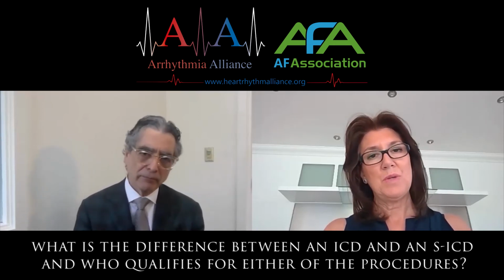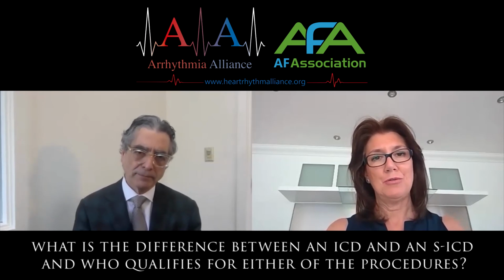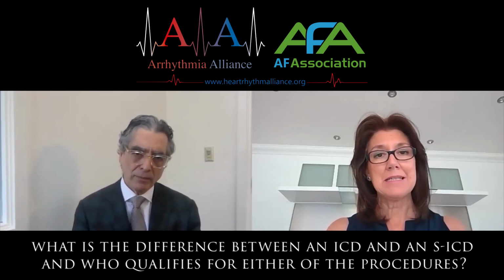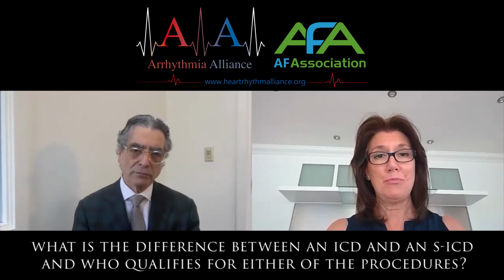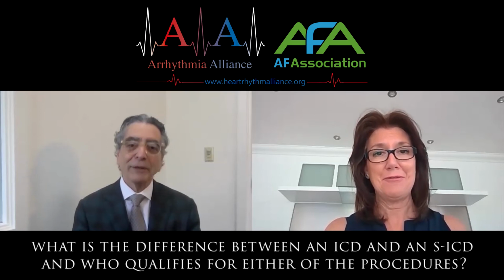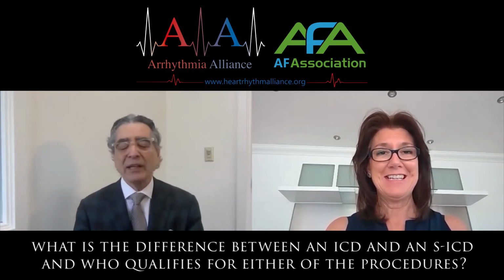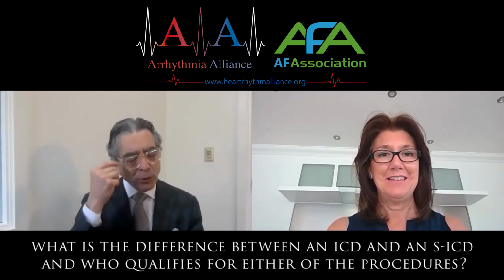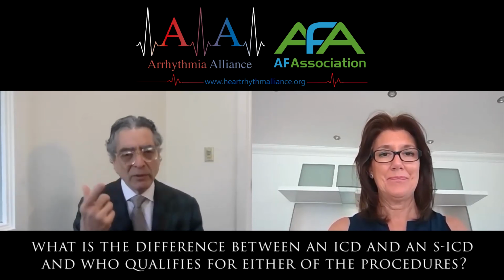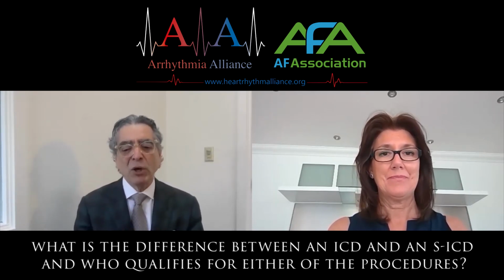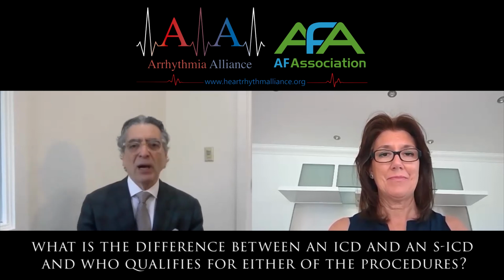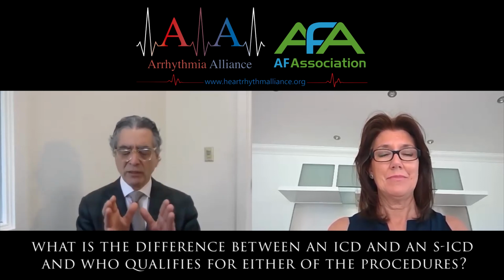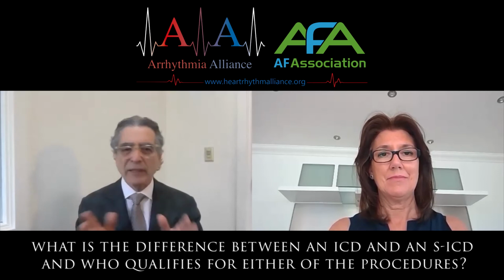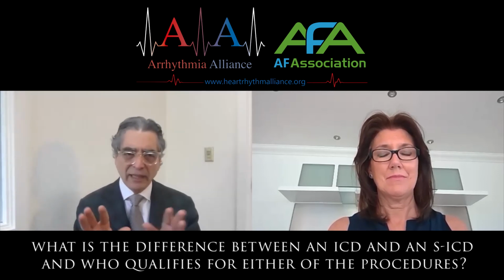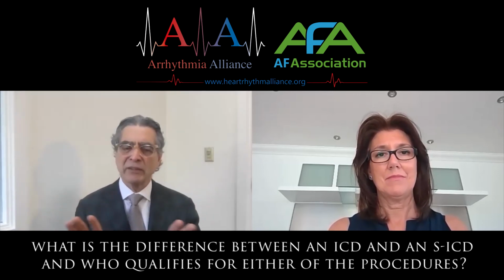And that's exactly what we tell patients when they have a shock. Although it's not pleasant, they should be grateful because it proves the device has saved their life. Yes, it's a very important thing for people to remember. Most people, the false positive rates where devices intervene, roughly 5 to 10% in that domain, depending upon the device.